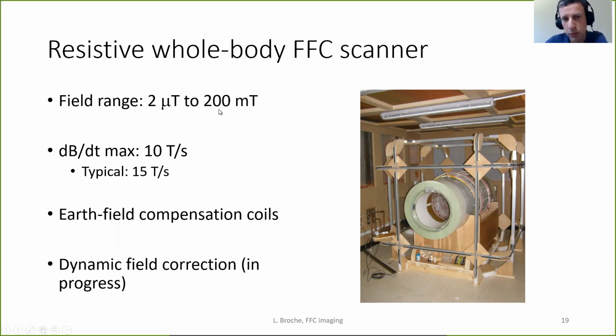It can reach about 200 millitesla and theoretically can go to 2 microtesla or below. It would depend on the level of care that you take to control the environmental field. So with a resistive scanner, the lowest range of the field depends on how well you can control the ambient field, which is responsible for the limitation at low fields. Anyway, you can also change the magnetic field at 10 Tesla per second. So that allows you to probe low magnetic fields quite quickly and avoid too much signal loss.